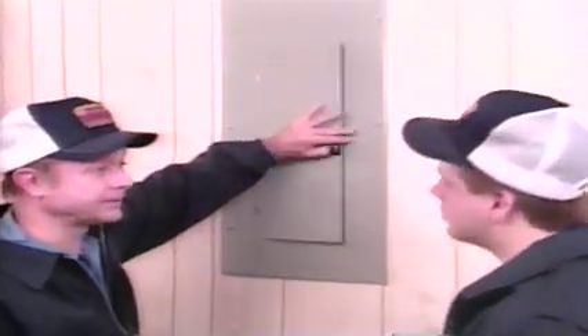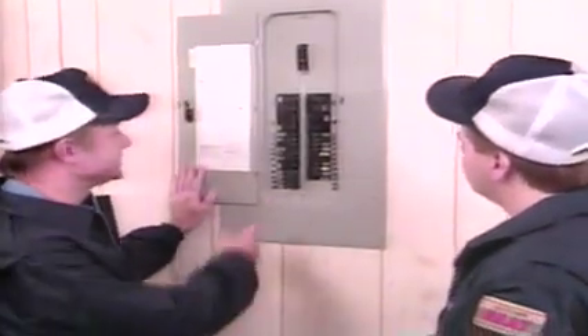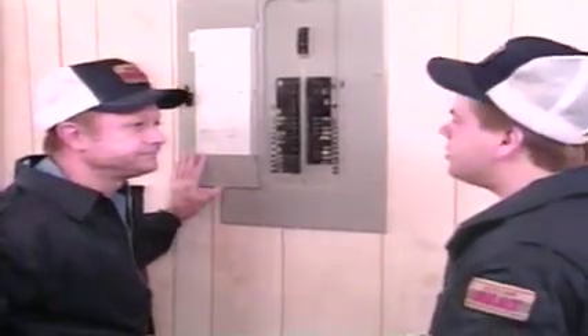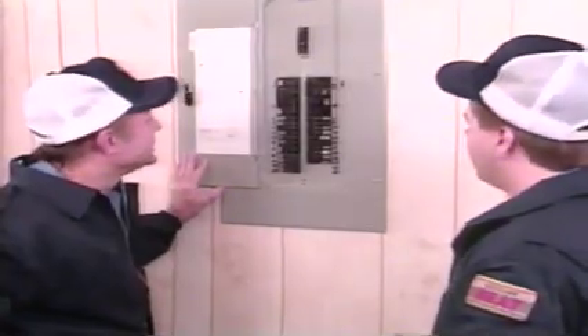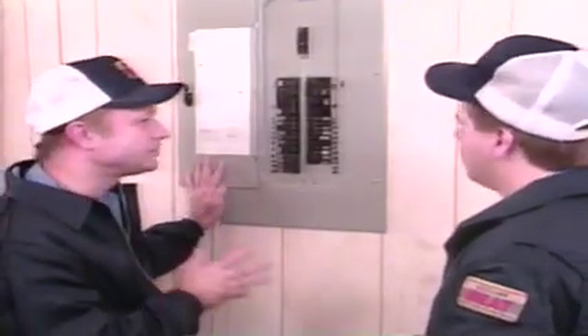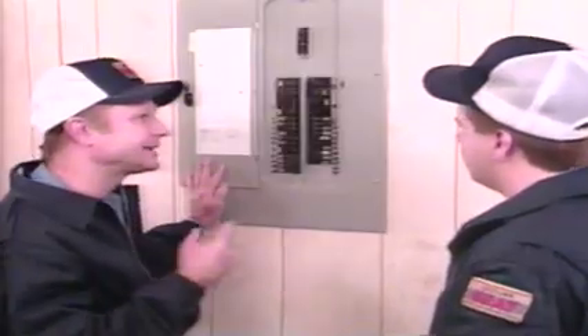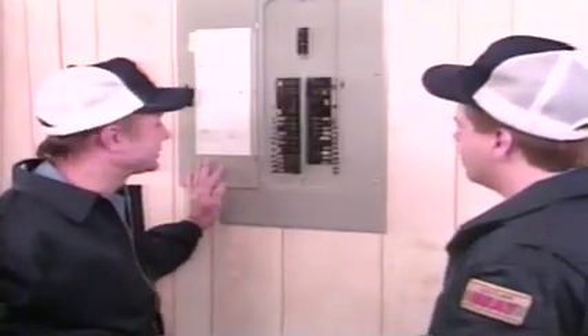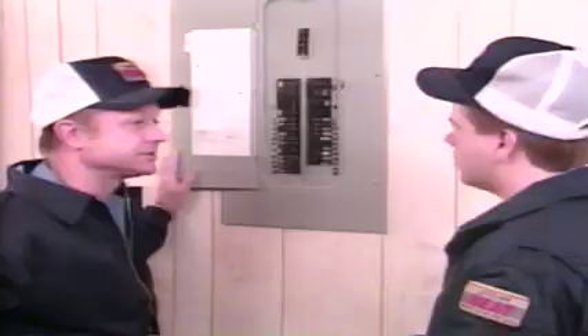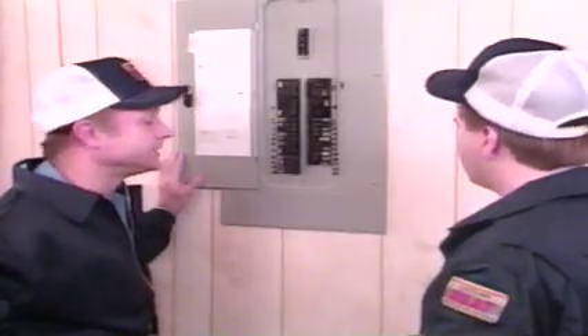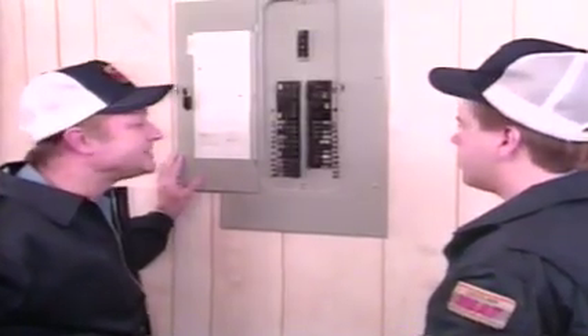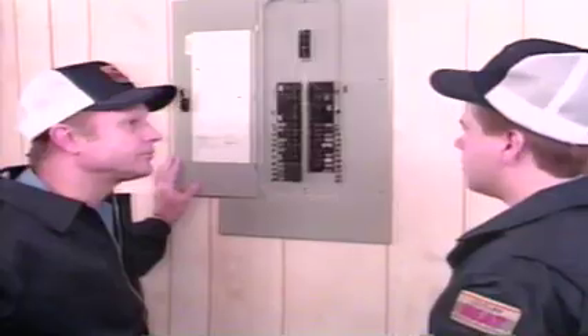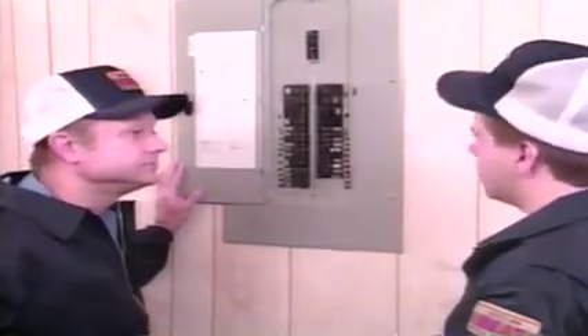The distribution panel. Now this one has circuit breakers. Well, the one at my house uses fuses. Yeah, they come both ways. Now the distribution panel serves 2 important functions. First, it distributes electric current throughout the house through branch circuits. Each one of the circuit breakers is a branch circuit. So when a fuse blows at my house, that's why some of the lights go out. Exactly, which leads to the second important function. It prevents dangerously high electric current from going through any one branch circuit.